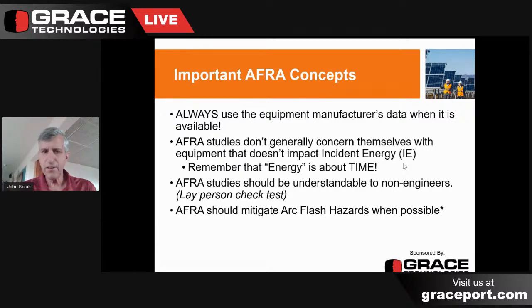Technically speaking, the standards that relate to these normally don't require us to try and lower incident energy, although some do. So I say that because it is technically legal to just calculate incident energy on equipment that will be exposed or accessed in the field and just label it. So you could label it with a very high incident energy level that would be actually unsafe at any speed in real life. And of course, I recommend we take that a step further and try to actually lower the incident energy through the use of engineering controls. That's the focus of this whole presentation. So let's go to the next slide.